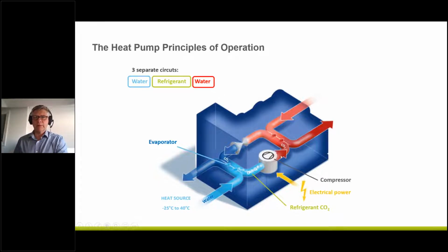And again, into the high temperature outside, and as I said, this is a gas cooler. So this is the heat source, and on the right hand side the heat sink. Water is coming in here into the heat exchanger or gas cooler. The inlet temperatures on the hot side in the gas cooler can range from 20 to 40. Actually, it can be above that, for example up to 46 degrees, depending on your heat source size. So we're not always limited to these temperatures.